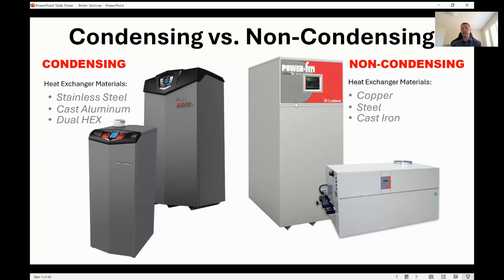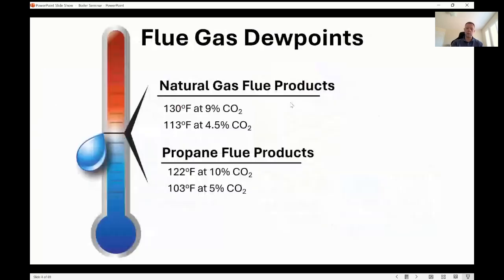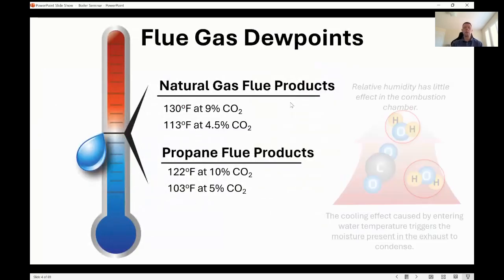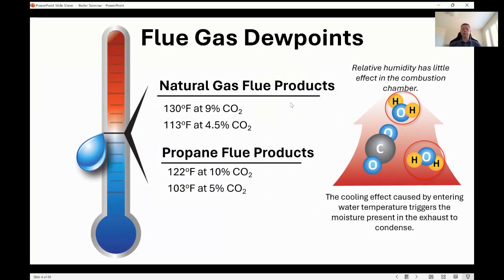Most non-condensing products use a material that's usually a little bit less expensive, something that can't handle condensate or doesn't need to. In most cases, what you're going to see out there is a copper tube, a steel tube boiler, or a cast iron sectional type product. So I said every boiler is really a condensing boiler. Condensation can happen in any type of boiler, just some are more inclined or able to handle it better.